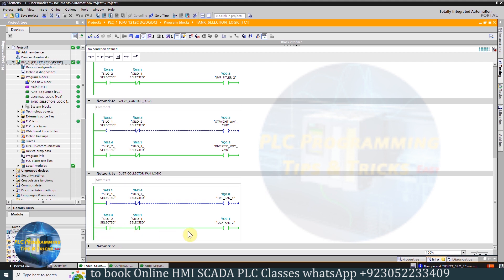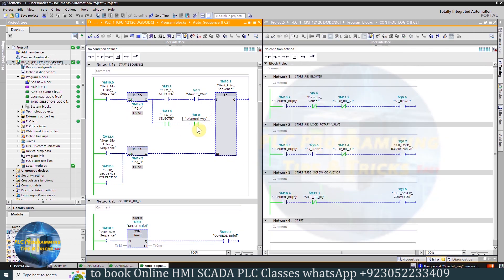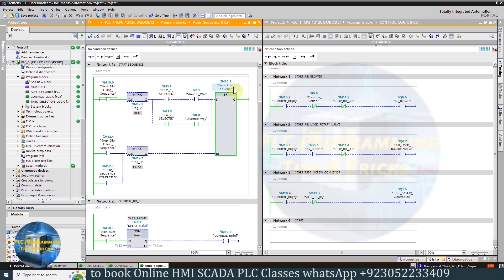In Network 5, the dust collector fan number 2 for silo 2 is now running. Next, opening the control logic and auto-sequence functions to monitor the ladder logic. The silo 2 selection bit is on and the valve-diverted-way feedback bit I0.0 is also closed. Now let's start the silo filling sequence by turning on bit M10.0. As soon as we turn on this bit, it holds on the start auto-sequence bit M10.1 and the filling sequence starts.